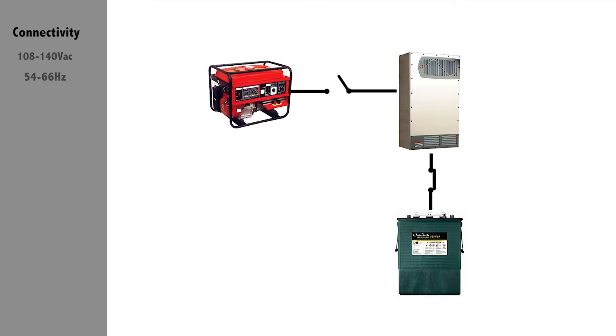First up is connectivity. For the inverter to accept the AC source, the generator must meet the following specifications: voltage range 108 to 140 volts AC per phase, frequency range 54 to 66 hertz. When these conditions are within the acceptable limits, the inverter will accept the generator power.